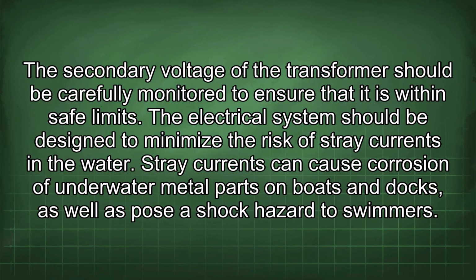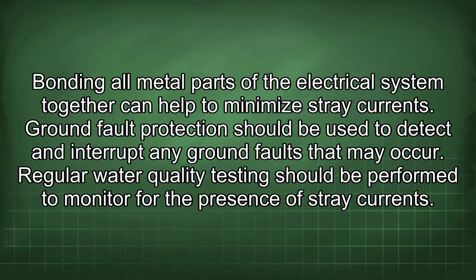The electrical system should be designed to minimize the risk of stray currents in the water. Stray currents can cause corrosion of underwater metal parts on boats and docks, as well as pose a shock hazard to swimmers. Bonding all metal parts of the electrical system together can help to minimize stray currents. Ground fault protection should be used to detect and interrupt any ground faults that may occur. Regular water quality testing should be performed to monitor for the presence of stray currents.